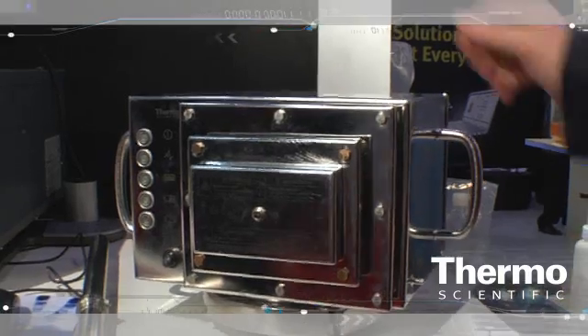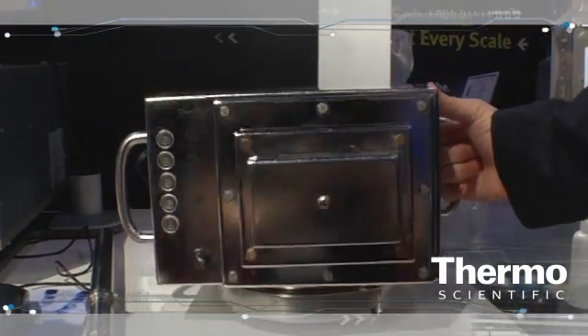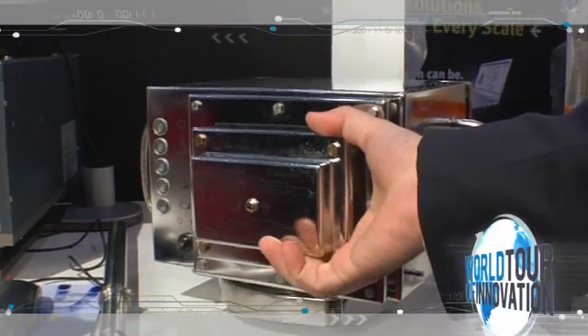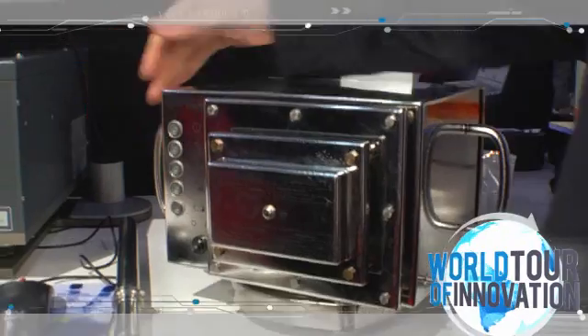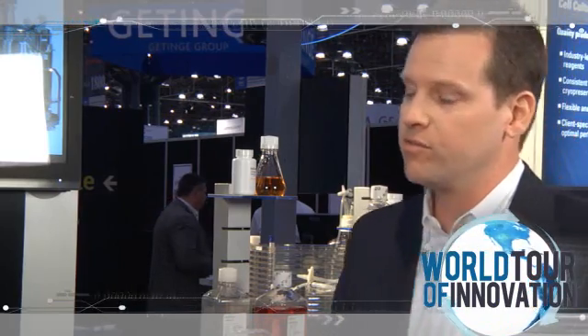This small system here is actually a very innovative product we came out with about two or three years ago — it's the Target Blend Analyzer. This fits onto pharmaceutical blenders and spins 360 degrees with the blender. The product is battery-powered, wireless-operated, and is an excellent analytical tool for customers needing to monitor their blends in real-time.